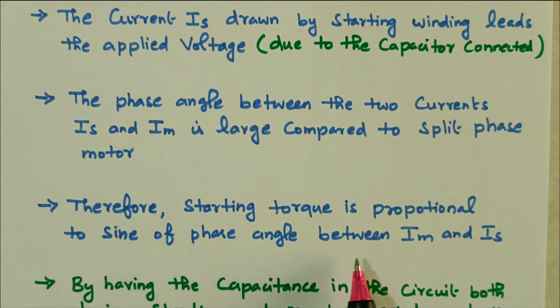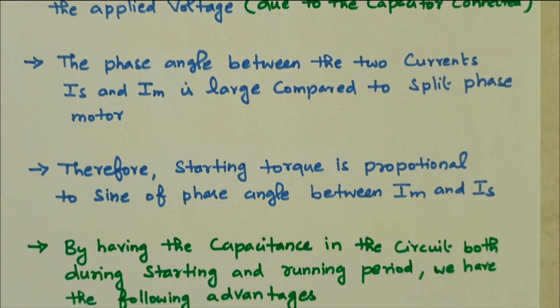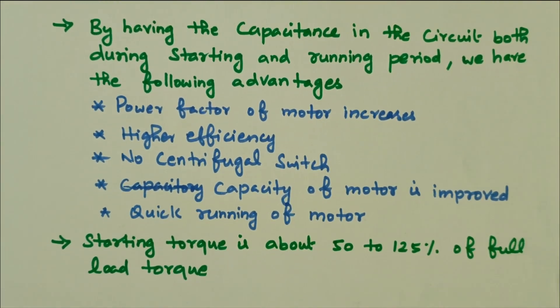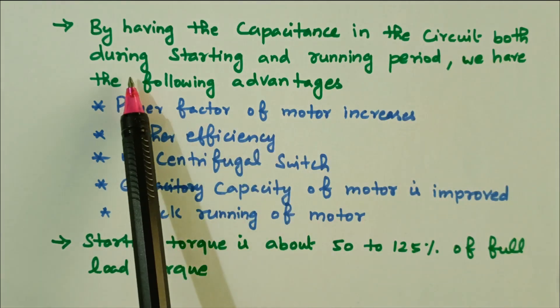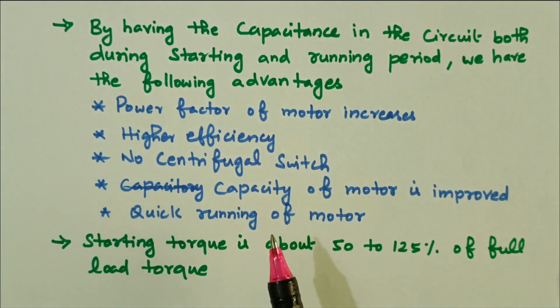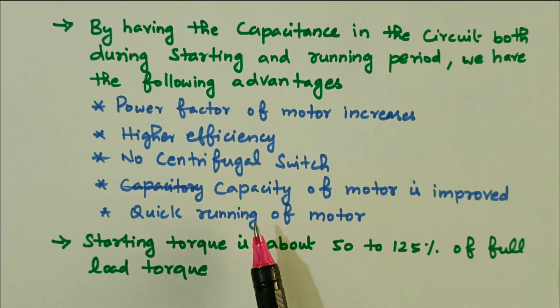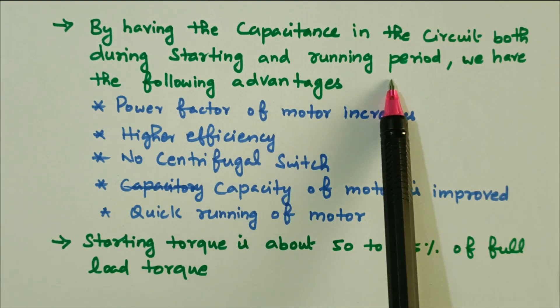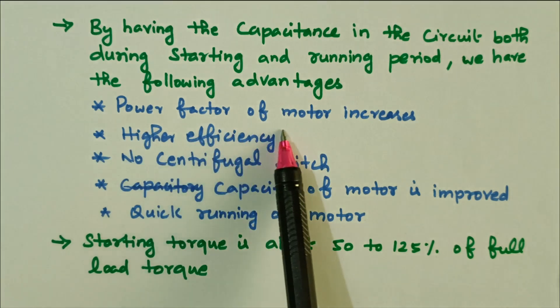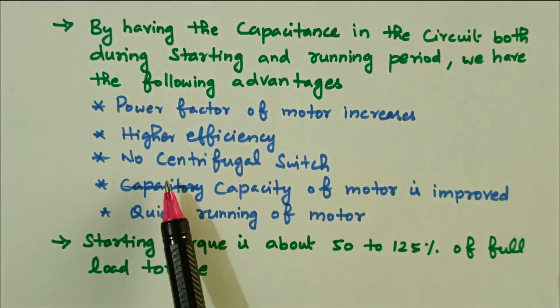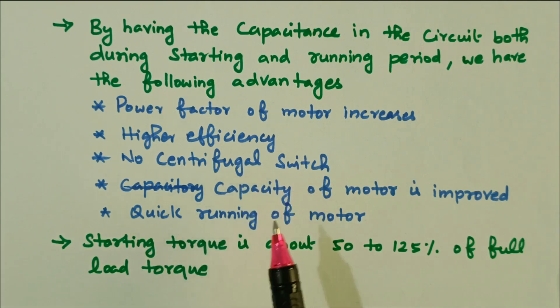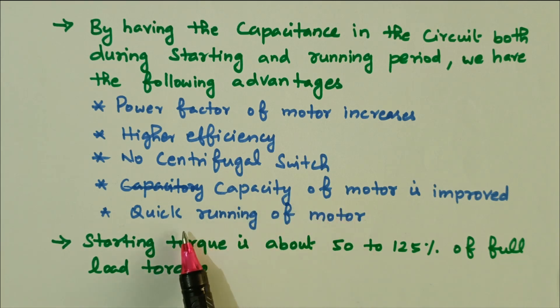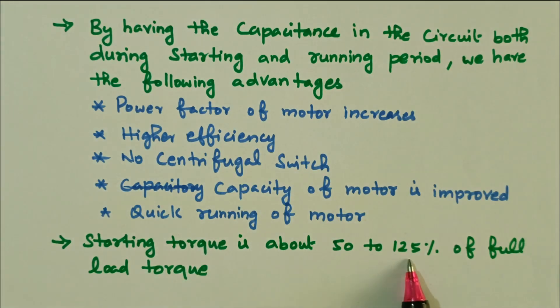By having capacitance in the circuit during both starting and running periods, the following advantages are available: the power factor of the motor increases, high efficiency is achieved, there is no centrifugal switch mechanism, the capacity of the motor is improved, and quicker running of the motor. The starting torque is about 50 to 125 percent of full load torque.